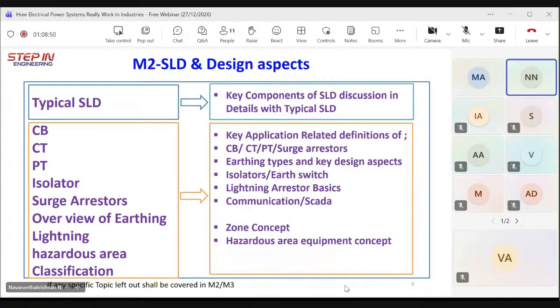Then we'll talk about surge arresters, how to select surge arresters, and we will not deep dive into insulation coordination. We will talk about only surge arresters, how surge arrester works, how the curve works, how the surge arrester rating is decided based on BIL. Okay, BIL is basic insulation level. Then we'll talk about basics of lightning, how the lightning evolved, the basic theory. Then we will talk about risk assessment, why we have to do risk assessment, on what basis we need lightning arrestor. Just one slide we will run, so that participants have a very good idea on the lightning system.